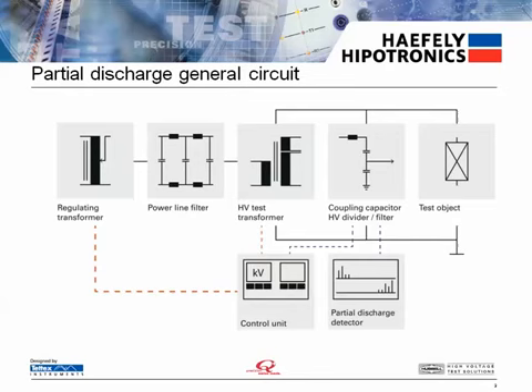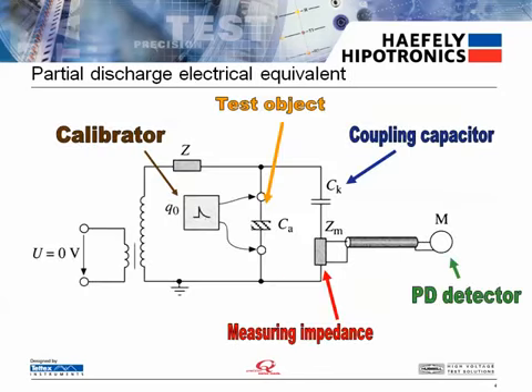This drawing provides a general circuit used for partial discharge testing. The partial discharge test setup requires a high voltage test source, which here includes the controls, regulator, line filter, and transformer, a partial discharge detector, a coupling capacitor with a low arm measuring impedance, and of course the test object. Missing from this circuit is a calibrator. Here's an equivalent diagram with a high voltage test source, PD detector, coupling capacitor and measuring impedance, and calibrator.